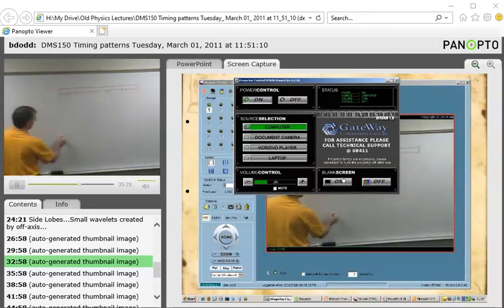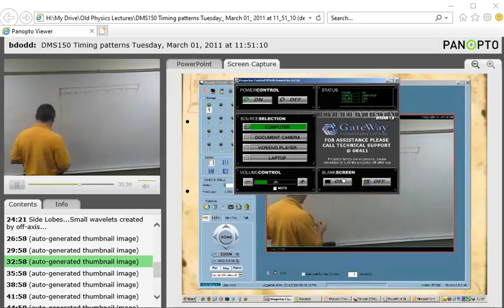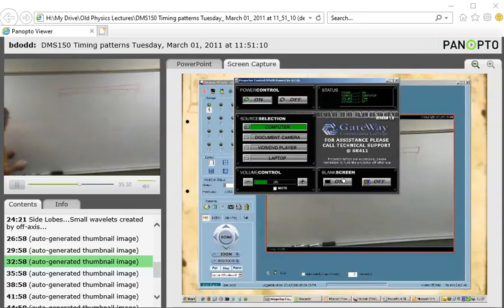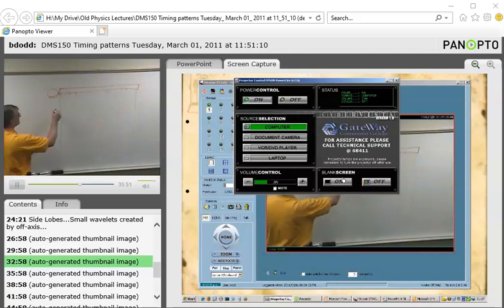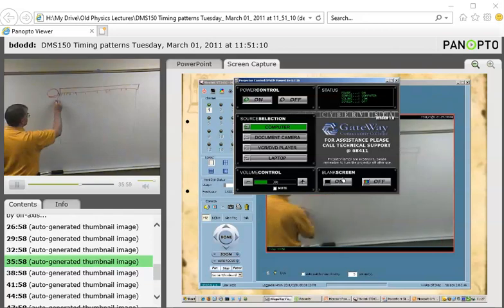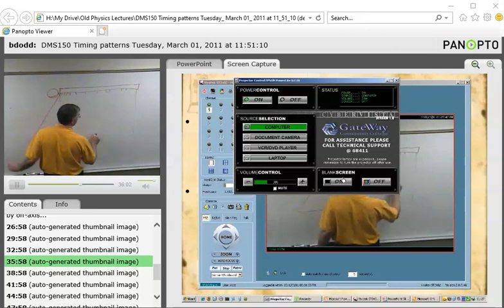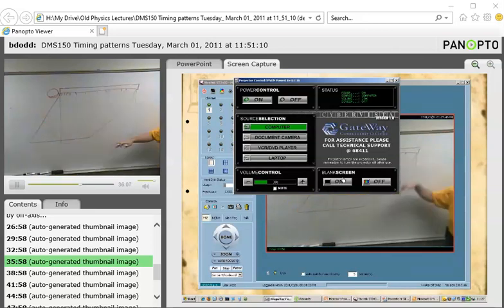image, instead of being a square box underneath the probe, the tech wanted to see something that was maybe over here. Well, how do we see that with our probe? There might be a mandible or something right here that we can't move our probe beyond. So some of the probes have the capability of using that same electronic steering, the building up of the wavelets into waves, and they can actually steer the image just like that. So instead of having a square image, it's got an image that's moved off to the side. Those of you that were in the lab yesterday, we actually did this, and we were able to see the image swung over to the side. Those of you that weren't there yesterday will get to see that today.